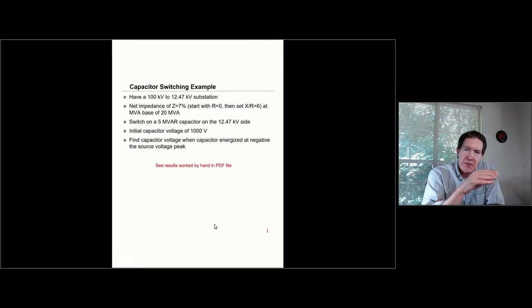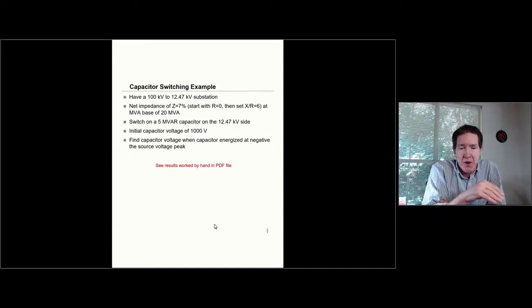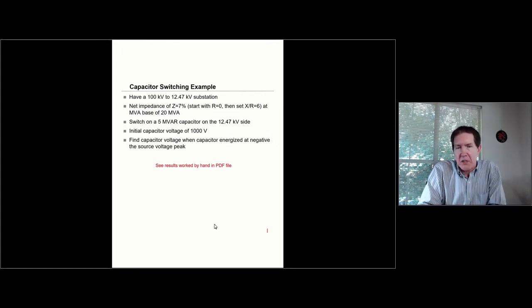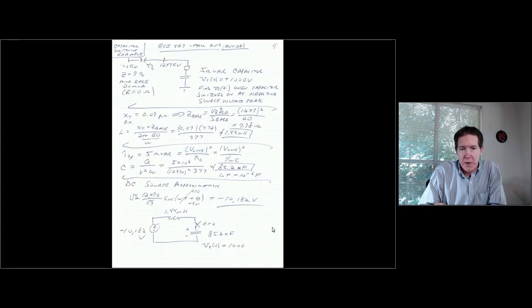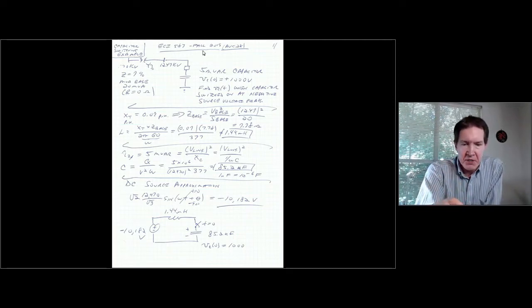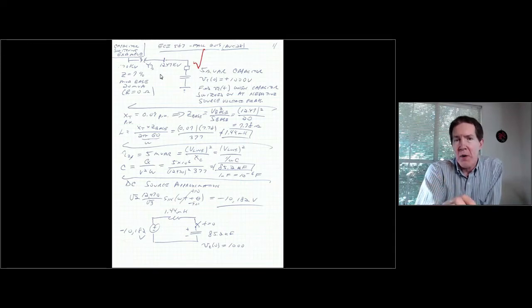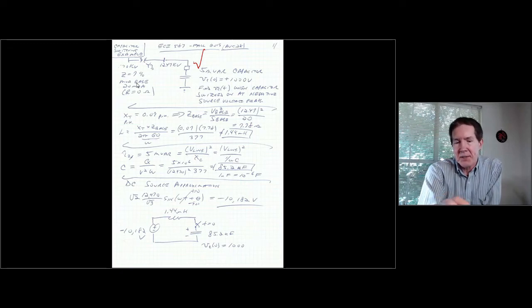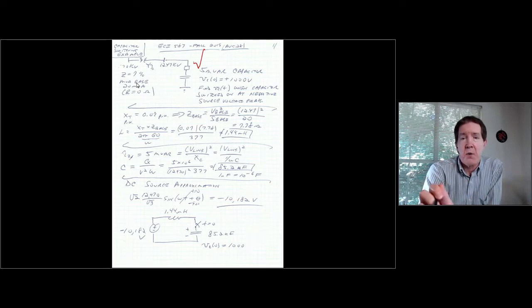The initial voltage can range in practice from plus or minus the peak value of the source voltage. At the top is a schematic of the circuit. It's Y-grounded on the secondary side, so the capacitor bank consists of three capacitors connected in a Y-grounded configuration. We're focusing on calculating one phase in this case.